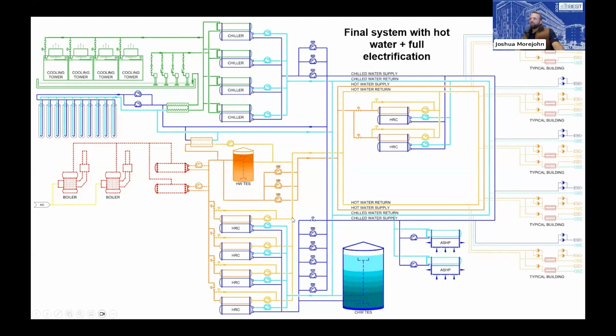We're able to run the heat recovery chillers for the majority of the load, then adding chillers with cooling towers for the peak summer loads where we need it, and adding a hot water storage tank. And then our existing boiler plant essentially being there as a supplemental heat source as long as we want to keep those boilers around.